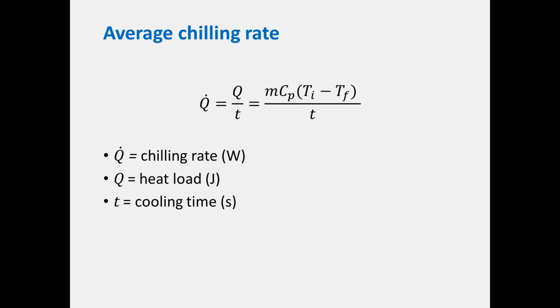That represents the minimum cooling power you need. In reality you may not achieve that cooling time, but if that is your target, it gives you the minimum required cooling rate. If your refrigeration unit can't handle that, you know you're going to struggle, and you might have to reduce the load going into that chiller.